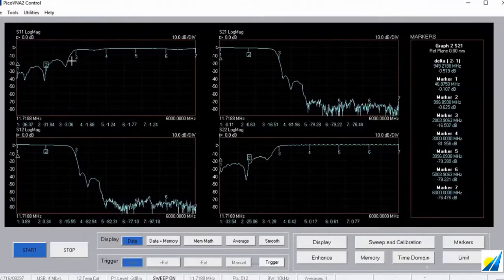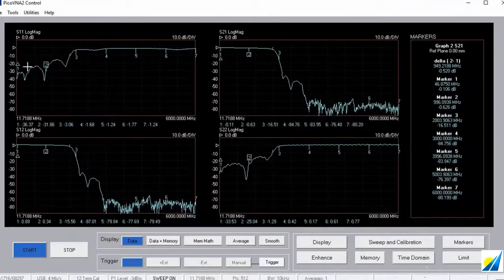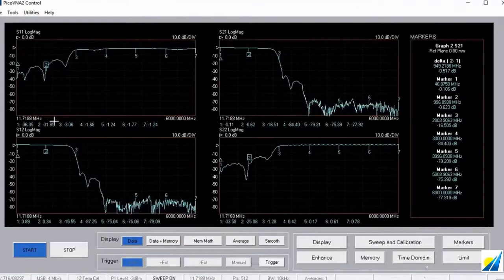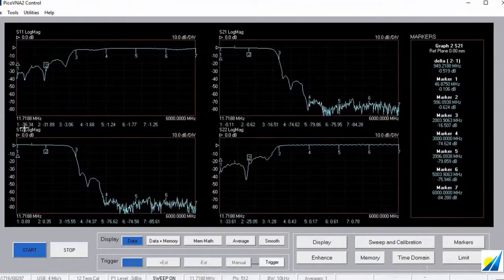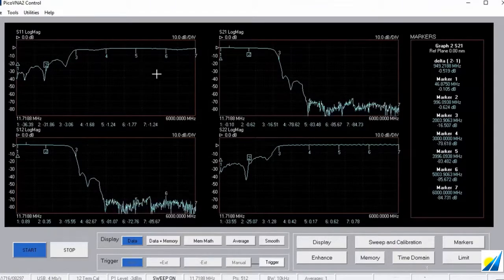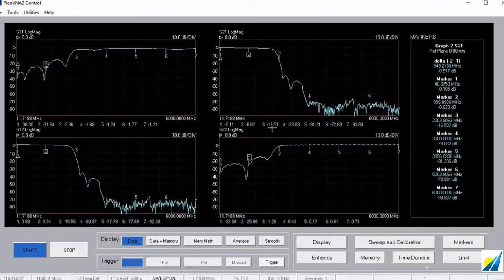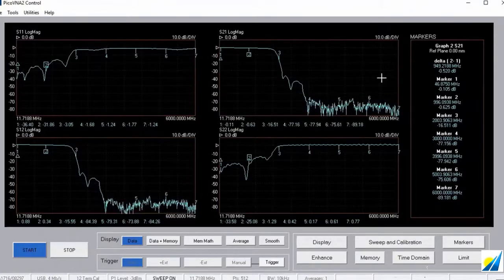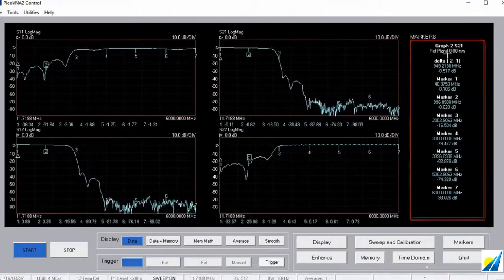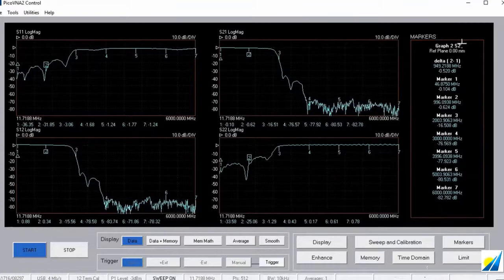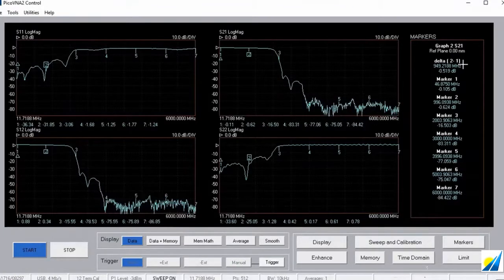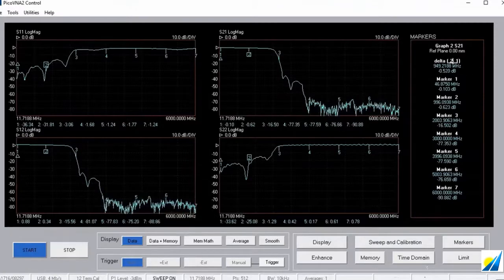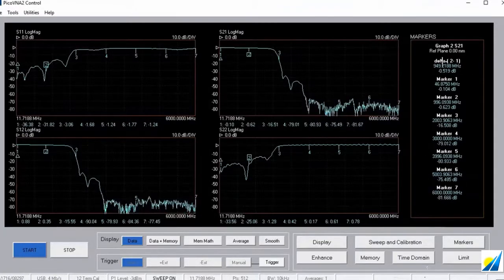Let me point out as well that we've got seven markers up on the traces here and you can see below the plots we've got low resolution readouts of every marker on every channel. So, convenient readouts at the bottom of the plots. Over to the right, you can see that I have a little bit more detail. I have for channel 2, graph 2 here, S21, you can see I've got frequency detail and a higher resolution readout coming off each of the markers.